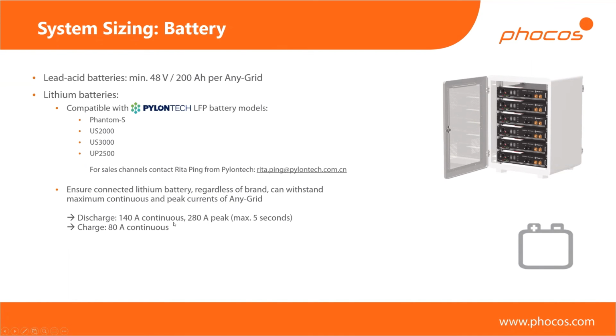For the discharge, we have much higher currents because we're dealing with an inverter which can potentially be used off-grid, which means that in such a scenario, it would not be supported by a second energy source. So all of the 5 kilowatts or 10 kilowatt peak, we need to be able to draw out of a battery if there's no PV available, for example. That would mean a continuous rating of 140 amps, and a peak rating to handle the 10 kilowatts for 5 seconds would be 280 amps per unit.